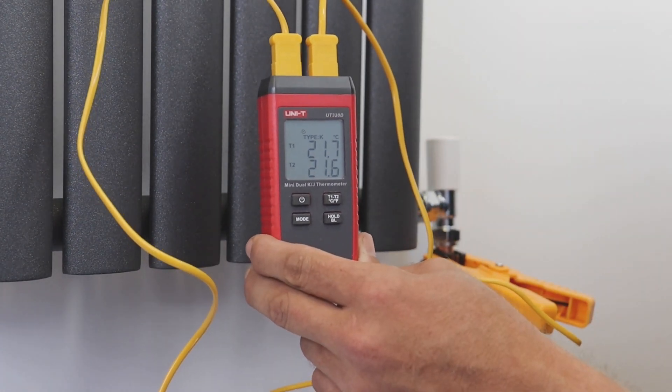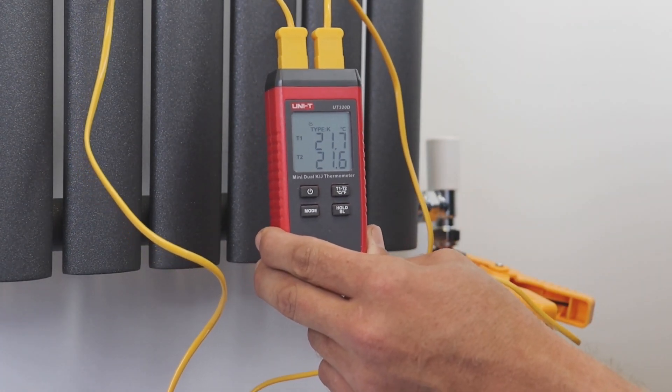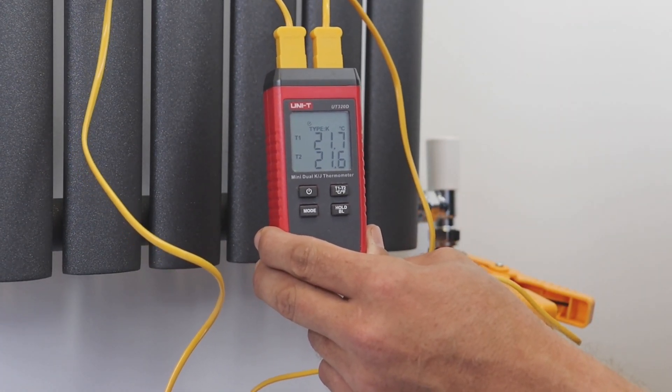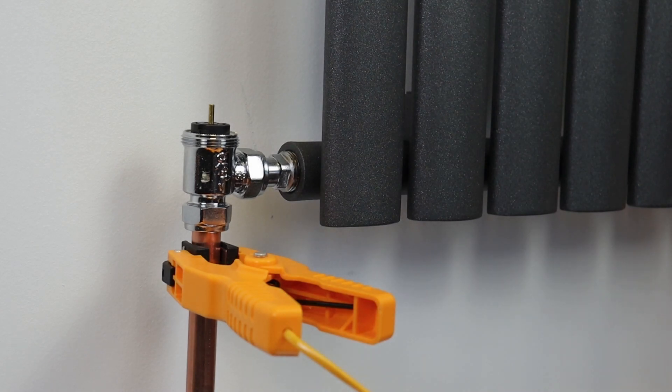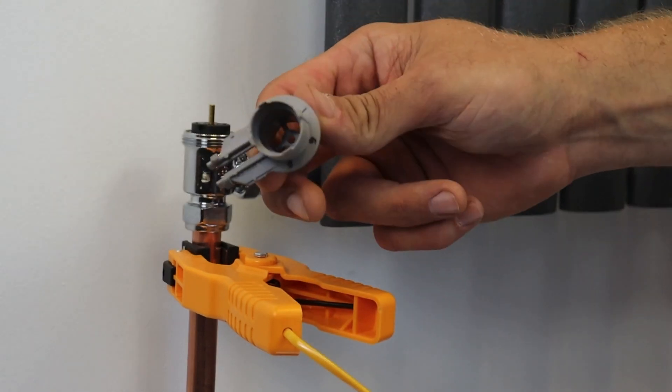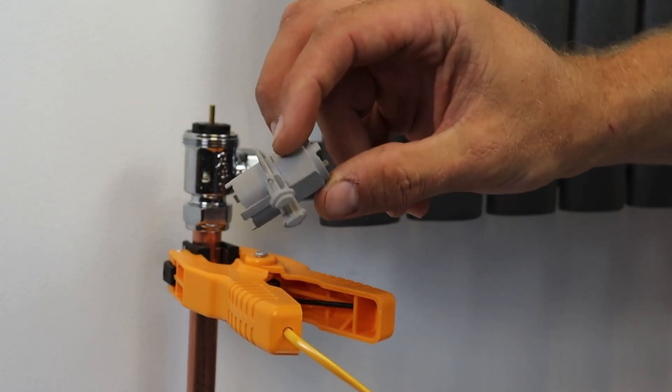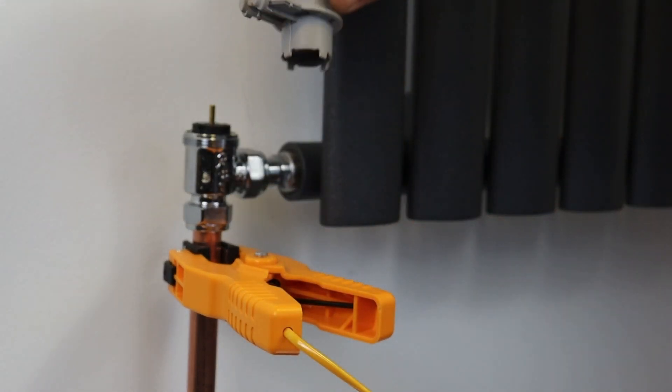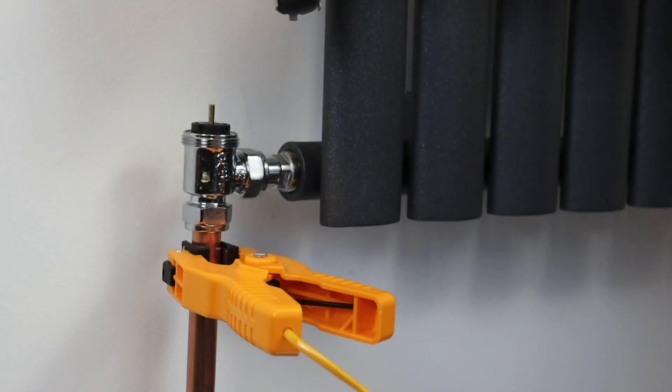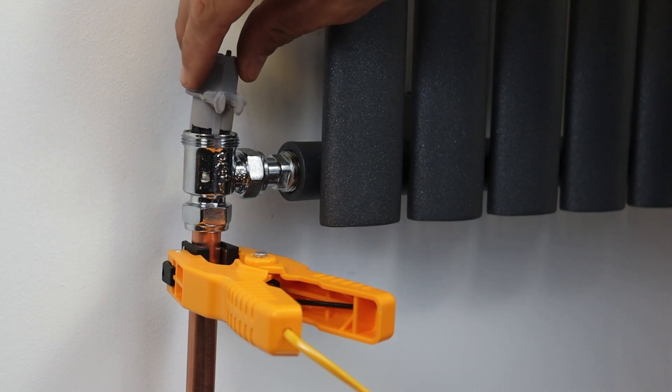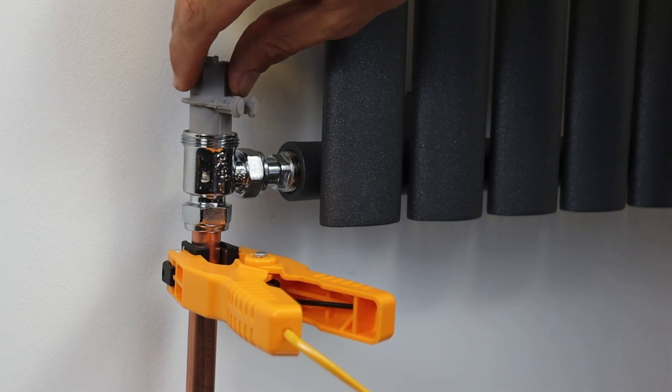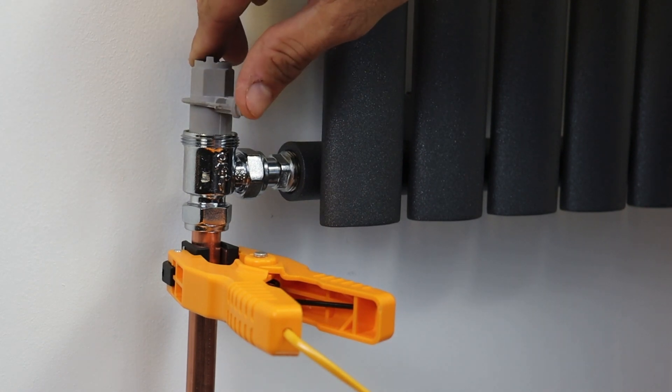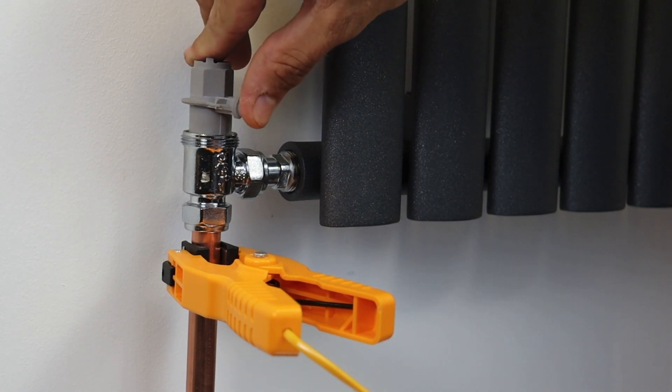The second method is to balance using the Drayton EB body. To do that you need one of these which is the Drayton balancing key. The way we balance with these is you use the bigger end, insert it around the top of the valve insert so that it engages into the clamp ring.